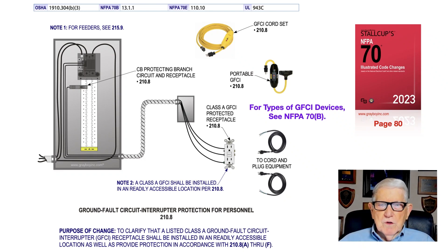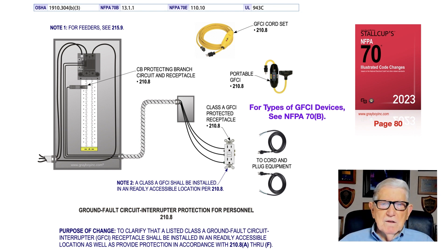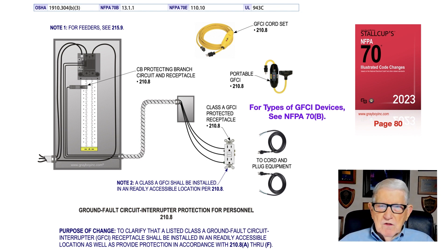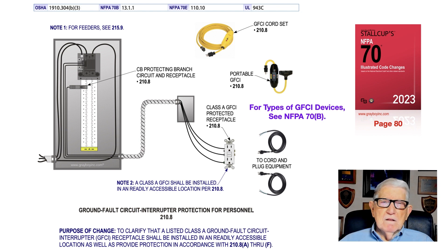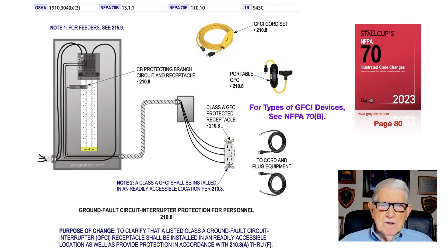This illustration deals with ground fault circuit interrupter protection for personnel in accordance with 210.8. We're on page 80 of the NEC. The purpose of the change was mainly to clarify that a listed Class A ground fault protection receptacle should be installed in a readily accessible location, as defined in article 100 of the code.